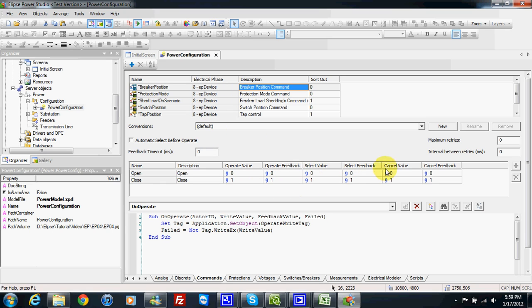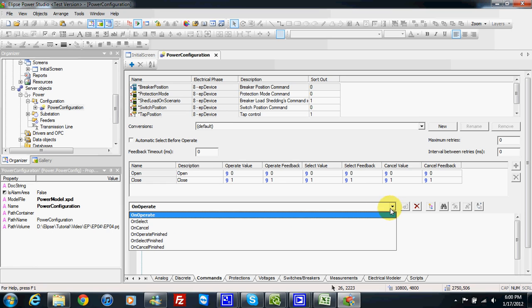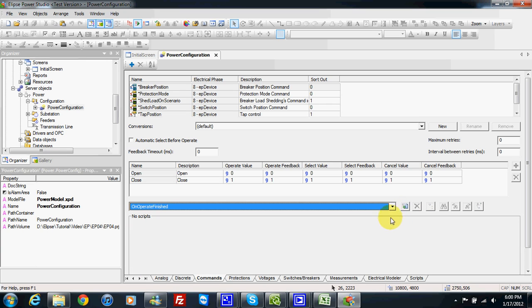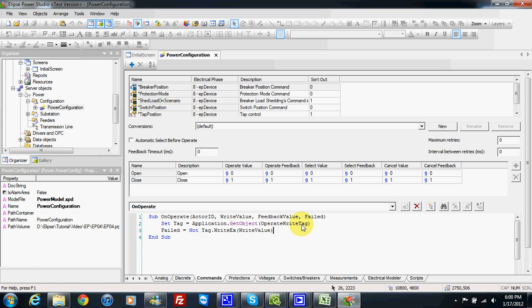Here we can apply a conversion, since each equipment may have different values. We can make several conversions for several kinds of equipment that require different values for the configuration of our command, also for different stages like operate, select, and cancel. I can also customize my code and configure myself the different scripts for the different commands. This way we can use the command to send breaker commands using different protocols like DNP3, IEC 61850, and IEC 103. We can design our command to properly send to different kinds of equipment using different protocols.